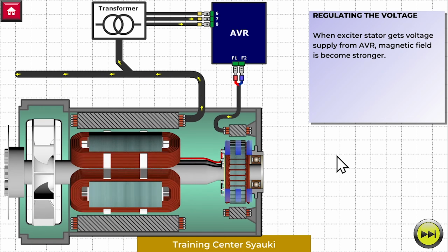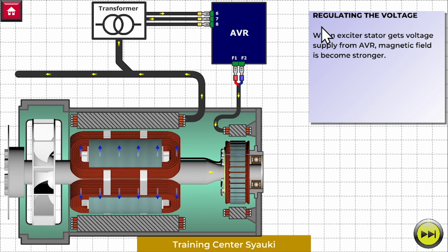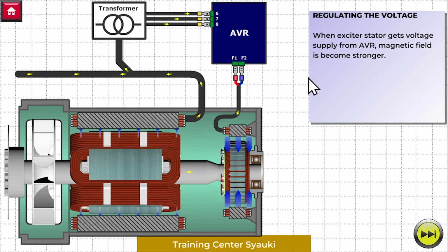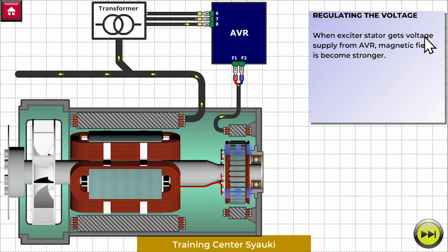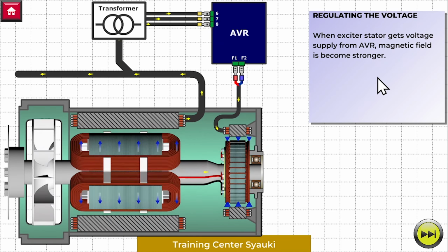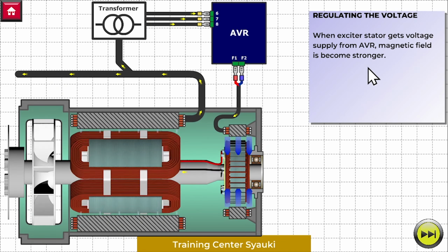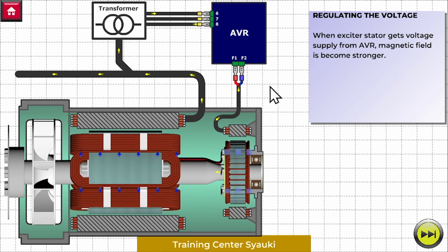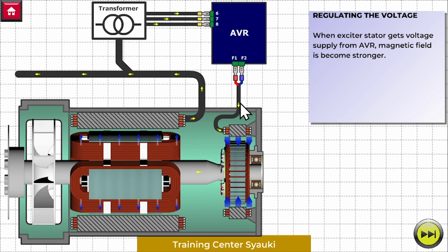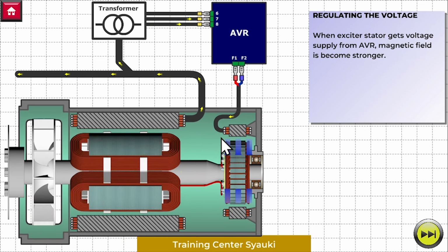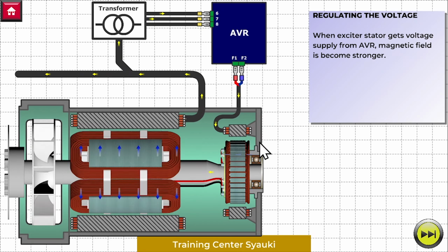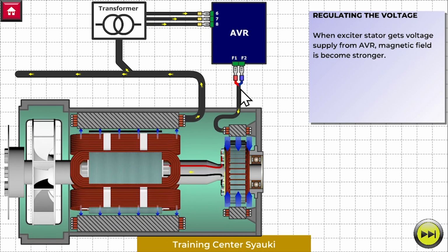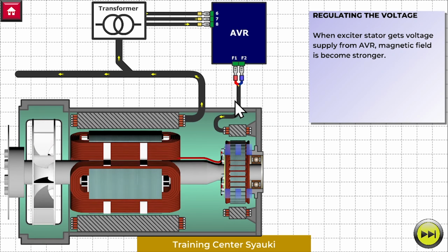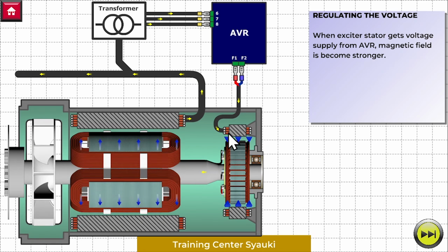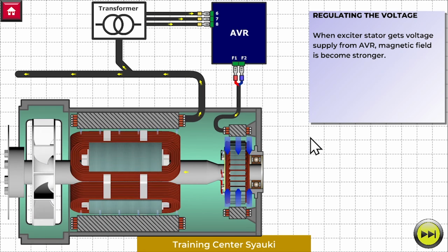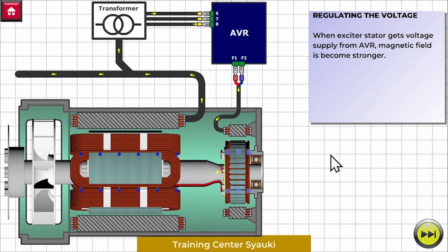Next we have regulating the voltage. When the exciter stator gets voltage supply from the AVR, the magnetic field becomes stronger. Before it gets voltage, it only has tiny magnetism. After this winding gets its supply, it gives a stronger magnetic field.